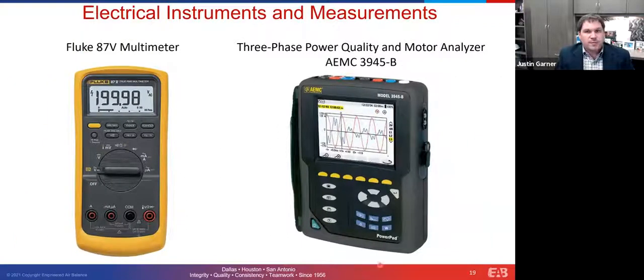I'm going to show you a couple of meters that we use here. This Fluke 87V is our standard meter here at EAB. And we like it because it's a fully functional multimeter, but it has that low pass filter. And so we don't have to worry about taking voltage downstream of a VFD. We can just turn that filter on and we get good clean measurements, among other things. This meter can do a full suite of measurements for amperage, voltage, resistance, you name it, it can do it.